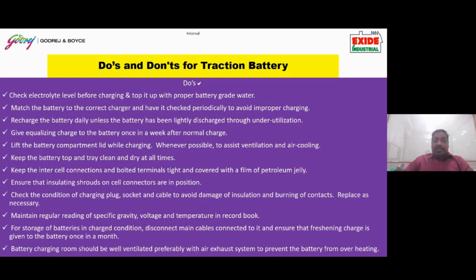Match the battery to the correct charger and have it checked periodically to avoid improper charging. Recharge the battery daily unless the battery has been lightly discharged under utilization. If the battery is used only 20% and 80% capacity is remaining, there is no need to recharge it. You can recharge it, but there is no necessity. However, if it is discharged below 50%, it mandatorily has to be recharged. Then periodical cleaning, equalizing charge, and keep the battery top tray clean and dry all the time.